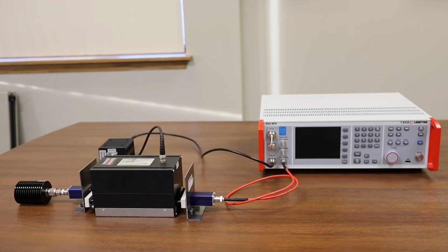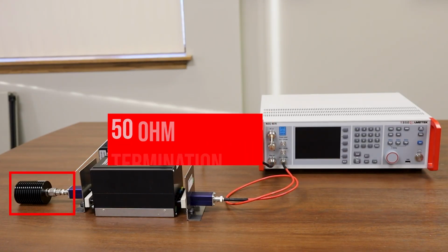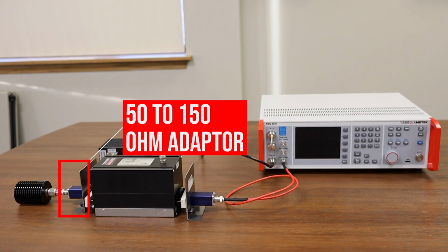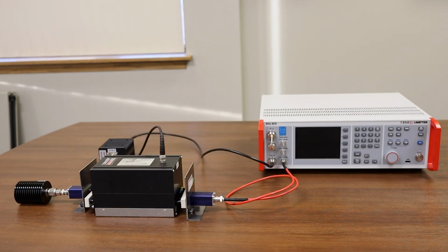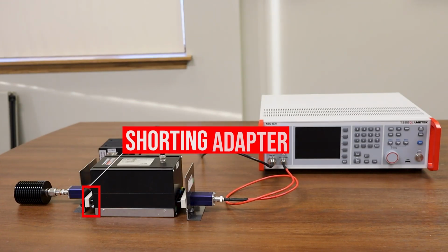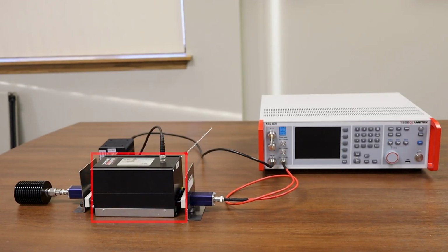Now we're taking a look at the calibration setup using the TESEQ NSG 4070. Let's start from the left and work our way right. Starting all the way on the left, we have our 50 ohm termination load connected to our 50 to 150 ohm adapter. The 50 to 150 ohm adapter is then connected to our shorting adapter connected to the coupling decoupling network. This is done on both sides of the CDN, both the power input and output going towards the EUT sides.